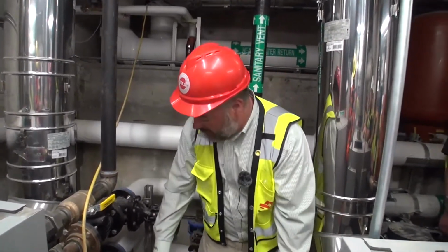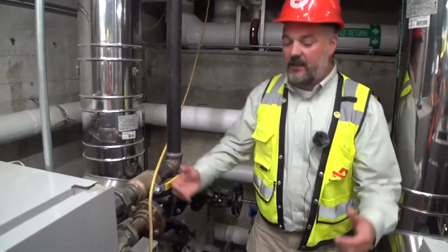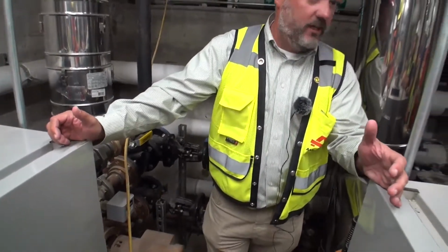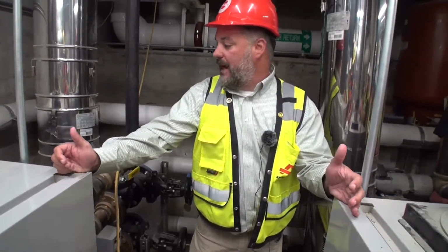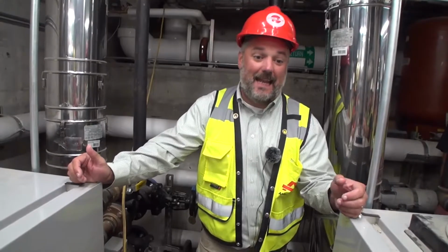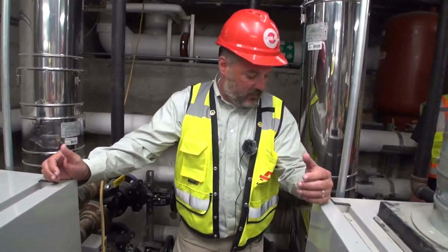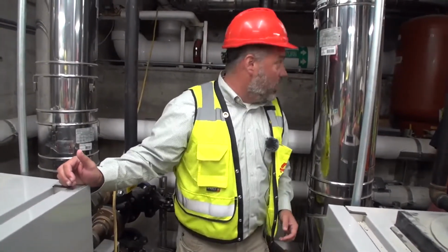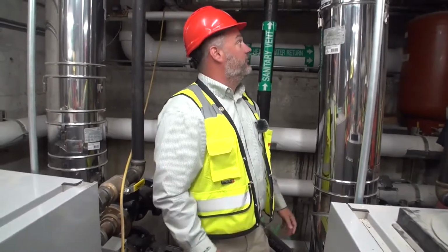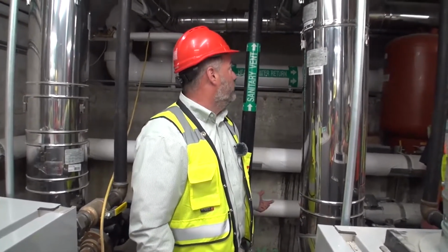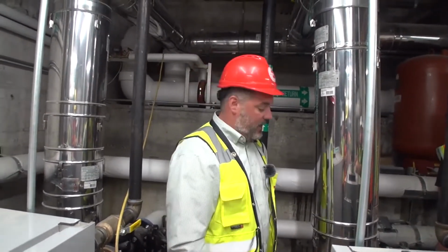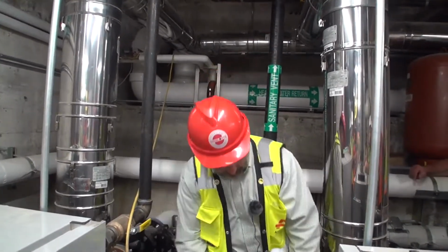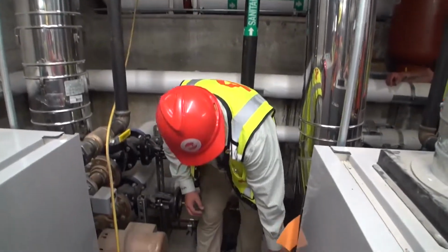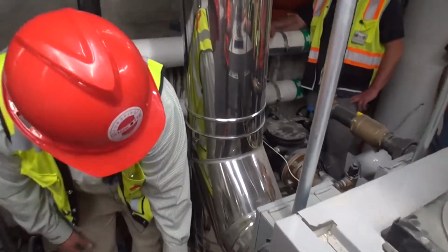We also have condensate neutralizers on here. These boilers are ultra high efficient units. They're over 95% efficient. They get up to 98% efficient depending on what stage firing we're at. So they will condensate. This venting is all stainless steel venting, so it's not going to corrode due to the condensation, but the condensation is going to flow back through. You can see the tubing down here with the neutralization.